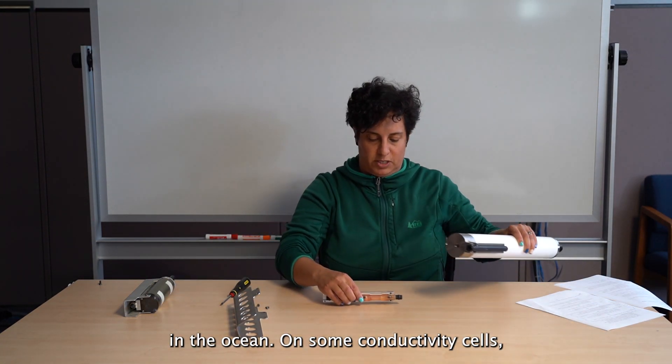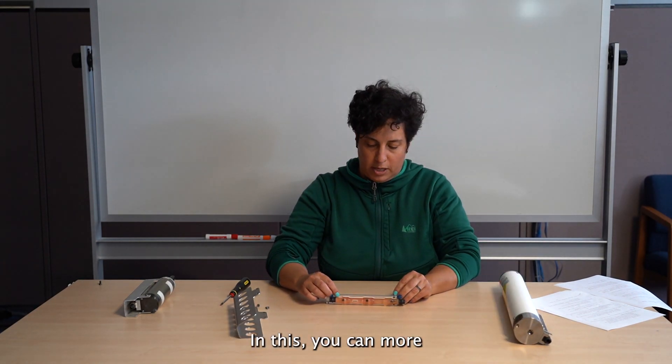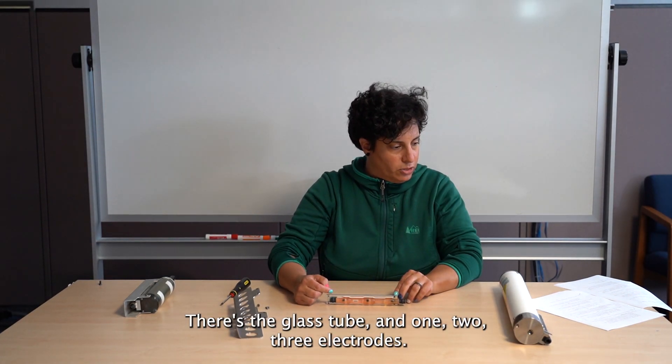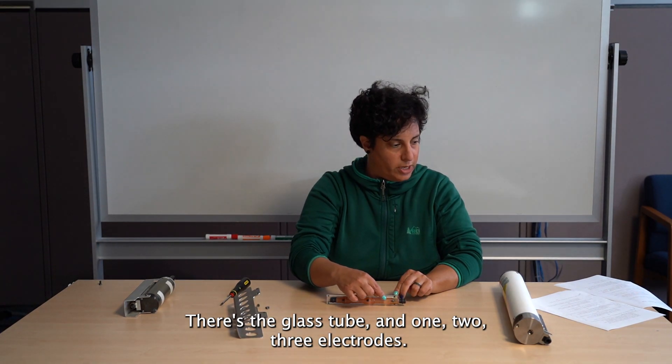On some conductivity cells, we use a pink epoxy like this one. In this, you can more clearly see the internal parts of the conductivity cell. There's the glass tube and one, two, three electrodes.